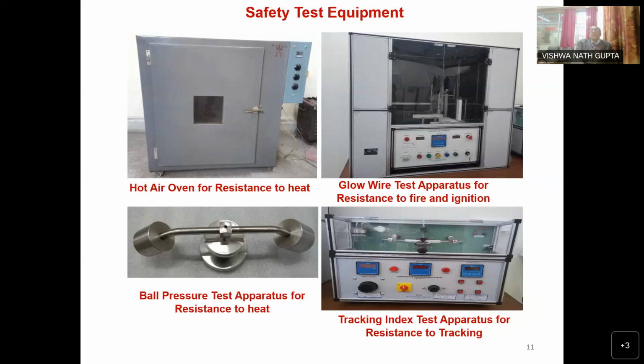This is the tracking index test apparatus for resistance to tracking. For switches or sockets used where there is some humidity, this ensures they do not give a shock when switched on, meaning the leakage current on the contact surface of the material should not exceed a value that would be hazardous to humans.